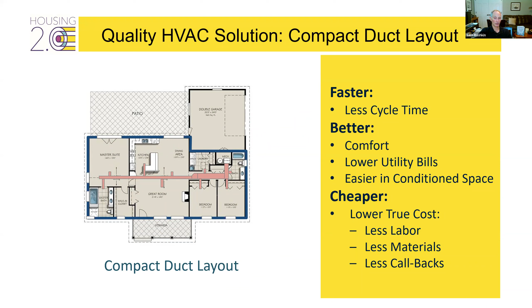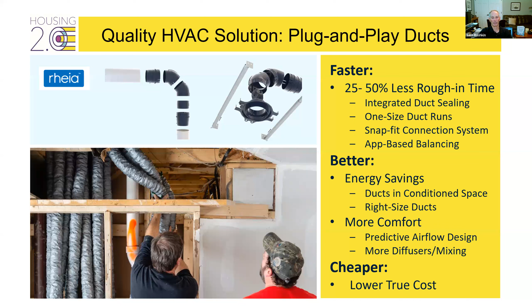There are also exciting new innovations like plug-and-play ducts that snap together airtight. These systems work with a big plenum on top of the air handler that has many 2.5-inch holes, and you run as many ducts to a room as needed, knowing each 2.5-inch duct carries about 25 CFM. So if I need 70 CFM for a great room, I might run three of these ducts with three grills. This is basically how it works in a house, and I'm excited about this innovation.